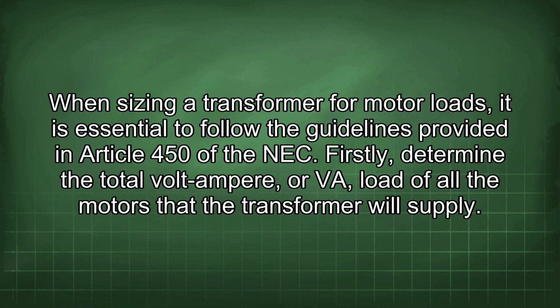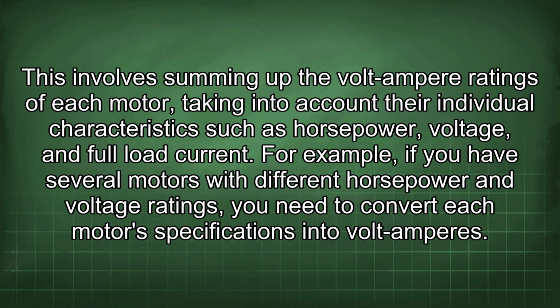When sizing a transformer for motor loads, it is essential to follow the guidelines provided in Article 450 of the NEC. Firstly, determine the total volt-ampere, or VA, load of all the motors that the transformer will supply. This involves summing up the volt-ampere ratings of each motor, taking into account their individual characteristics such as horsepower, voltage, and full load current. For example, if you have several motors with different horsepower and voltage ratings, you need to convert each motor's specifications into volt-amperes.